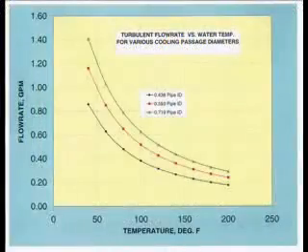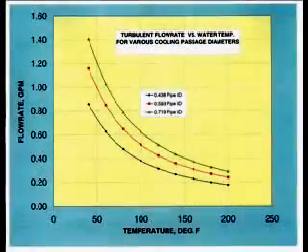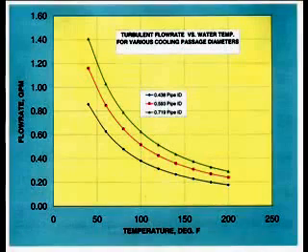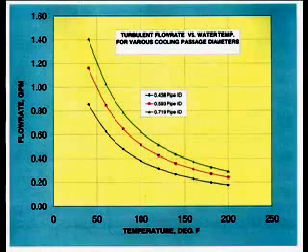Turbulence in a cooling circuit depends on the size of the channel and the speed and viscosity of the water. And since fluid viscosity increases with lower temperature, you could instead say that turbulence depends on channel size, water speed, and temperature.